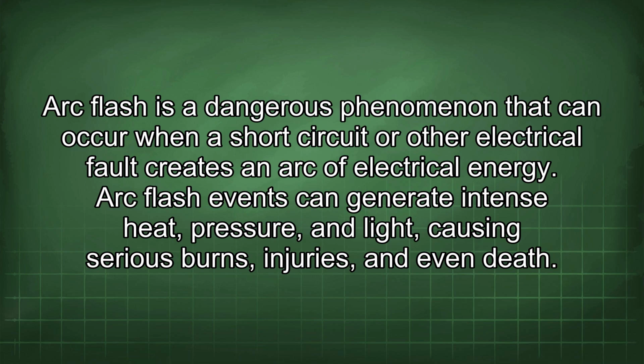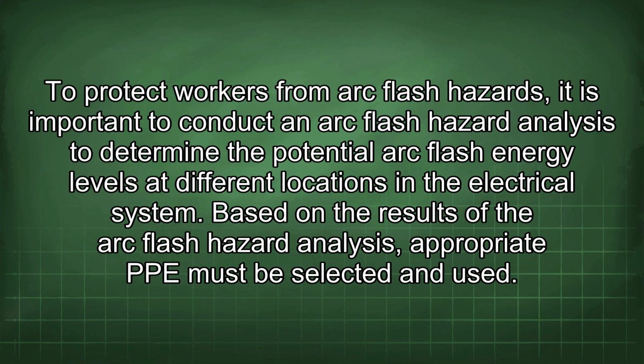Arc flash is a dangerous phenomenon that can occur when a short circuit or other electrical fault creates an arc of electrical energy. Arc flash events can generate intense heat, pressure, and light, causing serious burns, injuries, and even death. To protect workers from arc flash hazards, it is important to conduct an arc flash hazard analysis to determine the potential arc flash energy levels at different locations in the electrical system. Based on the results of the arc flash hazard analysis, appropriate PPE must be selected and used.